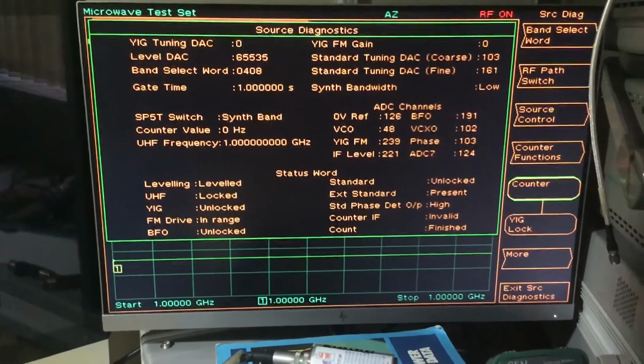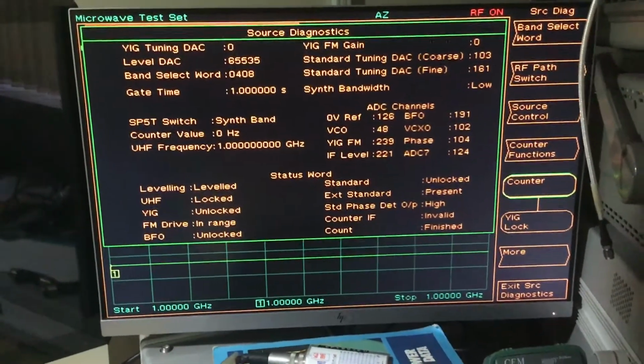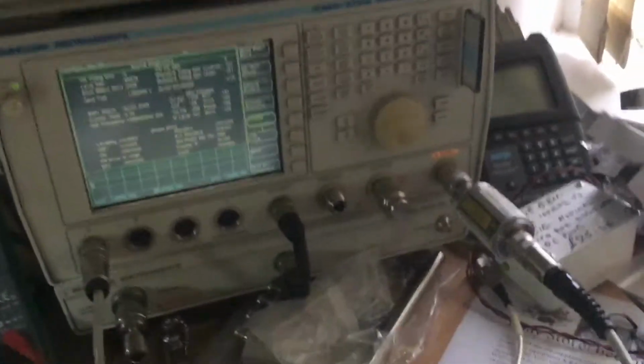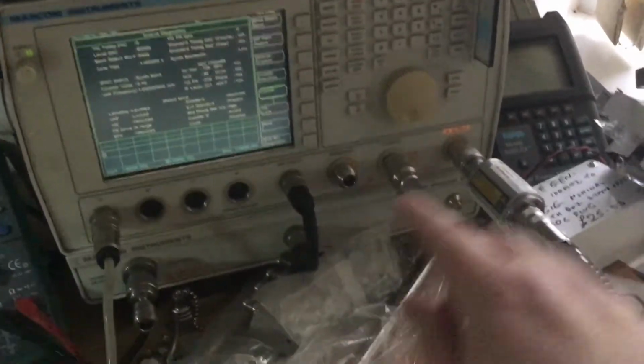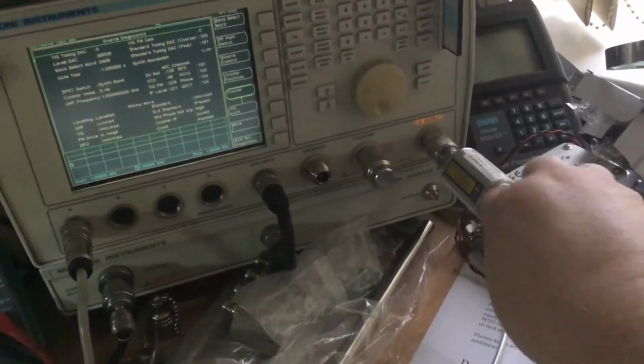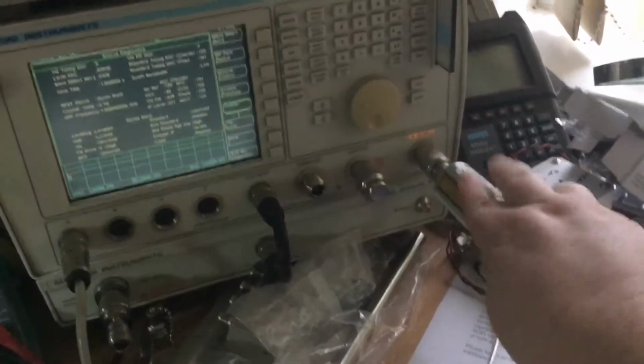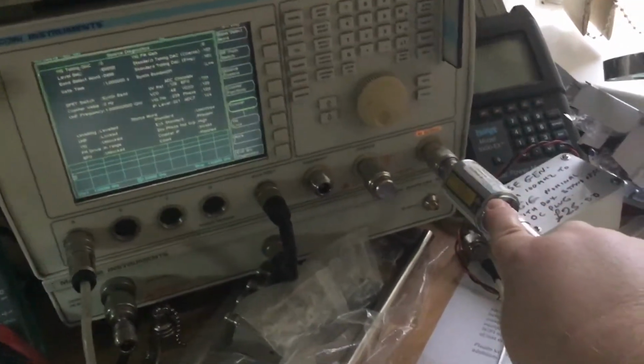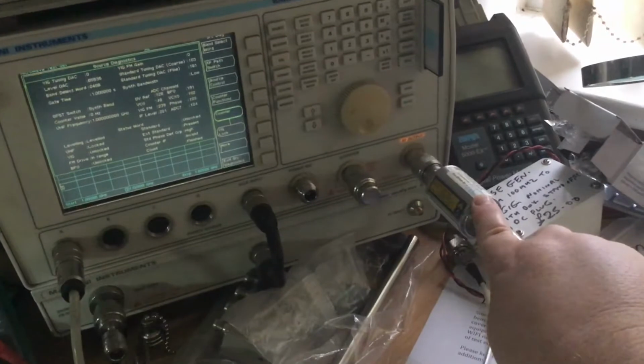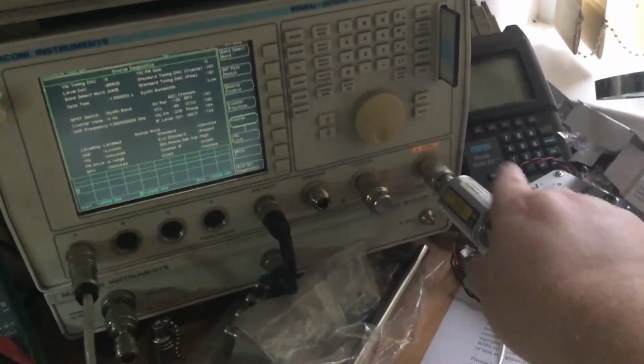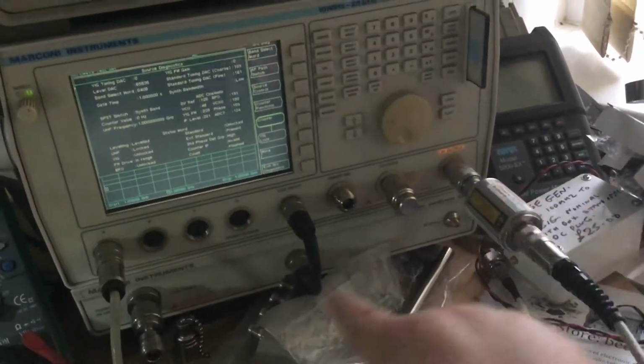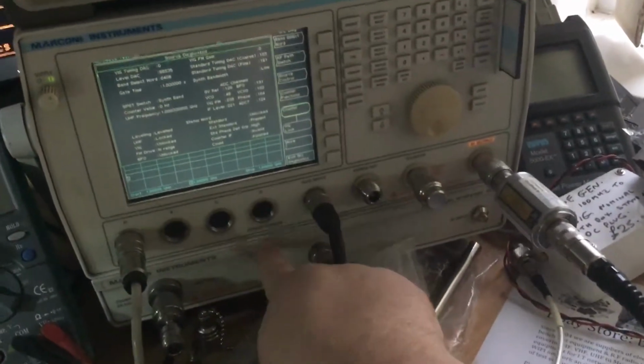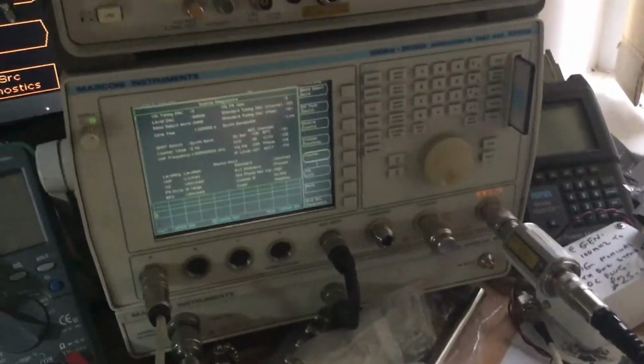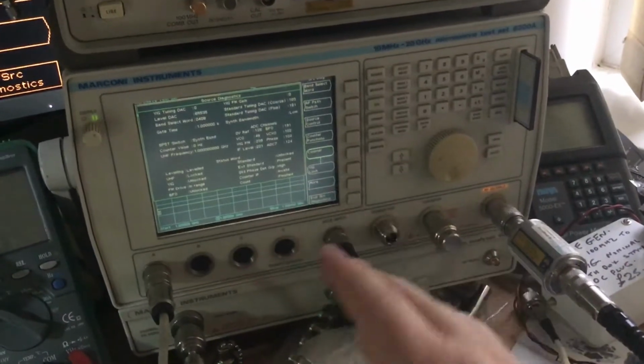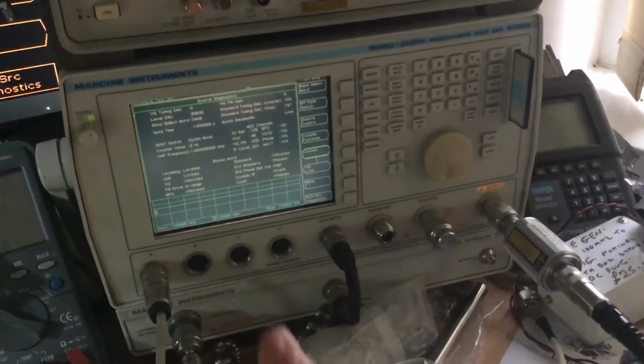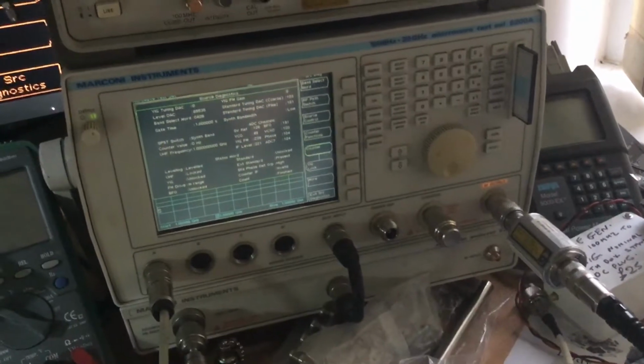So what happens is, when we calibrate the instrument under the calibrations function, we connect a power sensor. This is a scalar one at the moment. Oh no, that's a power sensor. We connect a power sensor like this to the RF output, and that then connects into port D on here. And we run a special diagnostics procedure that calibrates the instrument from 10 megs to 20 gigahertz in this case.